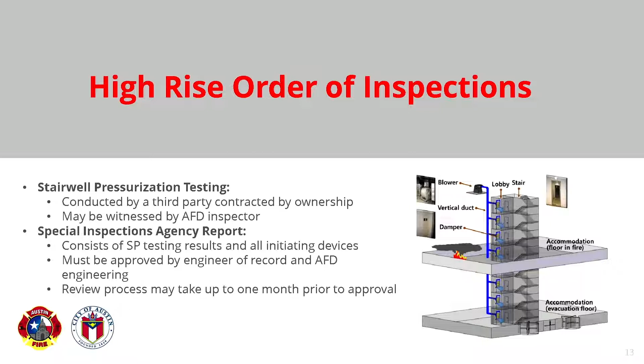They also have to be tested by the Special Inspections Agency that the ownership contracts to do their Special Inspections Agency report. Those can either be done on their own by the Special Inspections Agency, or they can do them with us. I personally don't mind doing them with them because they've got a lot of good insight when it comes to the mechanical systems in the building, more so than we do. Once that Special Inspections Agency report is completed, it gets uploaded to the compliance engine, which gets added to the Amanda system. Once it's added to the Amanda system, it gets assigned to an AFD engineer who then has 15 days to review it. Although the 15-day review is the standard, know that there are some steps that happen prior to that clock starting. So I normally say you should factor in a month to get that approved.